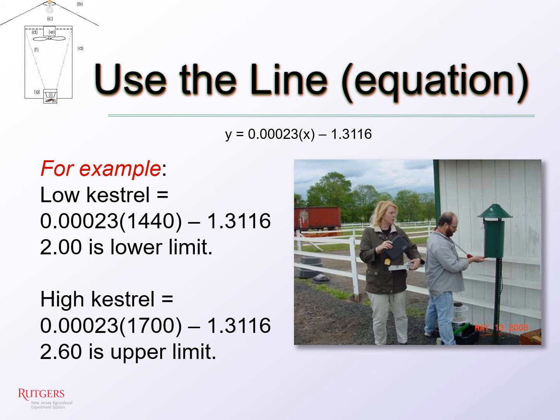The equation in the previous example is y equals 0.00023 times x minus 1.3116. To find the lower limit, the x is replaced with 1440, and that calculates to 2.00 rounded down. The upper value is found by substituting x with 1700, and this value calculates out to 2.60 rounded up. So this particular handheld Kestrel anemometer will show values between 2.00 and 2.60 for properly calibrated light traps.